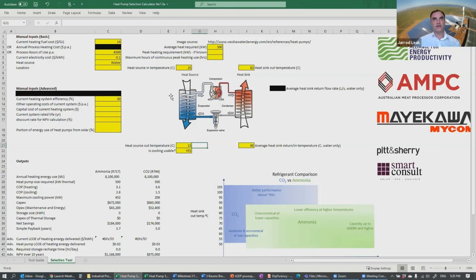From there, you can look at different sizes of the heat pump, or account for a peak requirement such as a CIP load in the morning—say in the mornings you've got a 700 kilowatt load for 1 hour. The system will also quickly do a back-of-the-envelope calculation for thermal storage and put that into the model, so that way you don't need to size the heat pump for the same capacity as your current steam boiler.